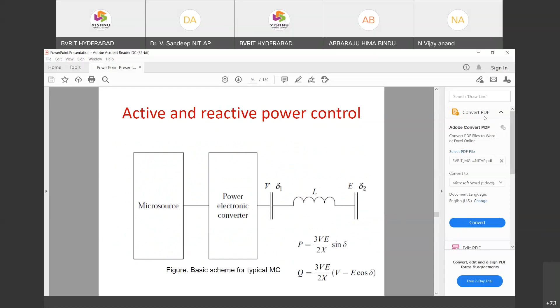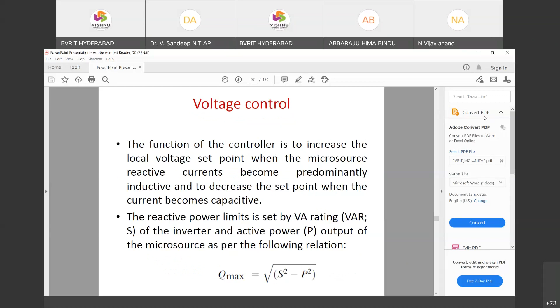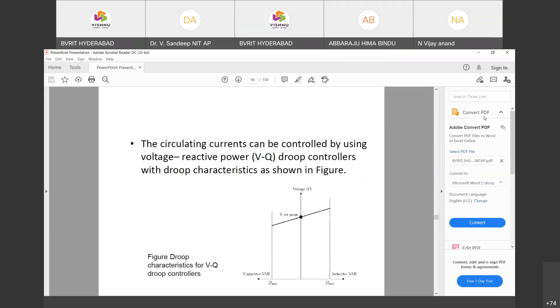So now what we are discussing is voltage control. How do you control the voltage is predominantly based on the nature of the current, that is inductive and capacitive. If the current is inductive, then we need to increase the voltage set point, whereas in case of capacitive, we'll decrease it. Going back to the previous slide, it shows if the inductive currents are rising, then the voltage set point needs to be increased, and if it's capacitive in nature, you need to reduce the voltage set point, based on the droop characteristics of V and Q, and we are going to set the voltage control. This is a very fundamental phenomenon in microgrids or any renewable energy technologies.